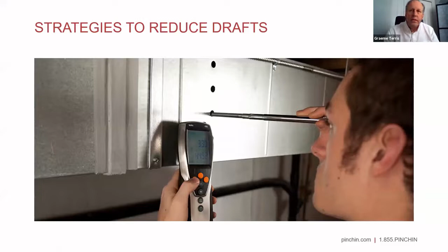So how do you reduce drafts? And drafts are the big thing. If what Jeff was saying about the reduced humidity and reducing your droplet size makes them more buoyant, then drafts become really important. If you've got less occupancy in your space, maybe that's not quite as relevant in a dentist surgery, but in an office certainly, you've got less occupancy, you've got less cooling load. If you've got less cooling load, you can turn your air volumes down a little bit, you can put more fresh air in, you can bring less recirculated air back.